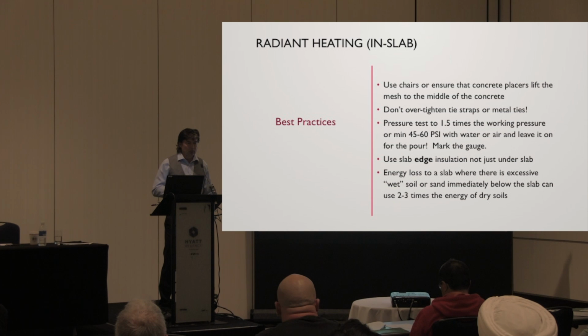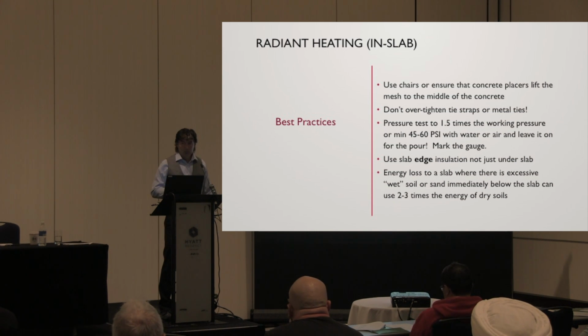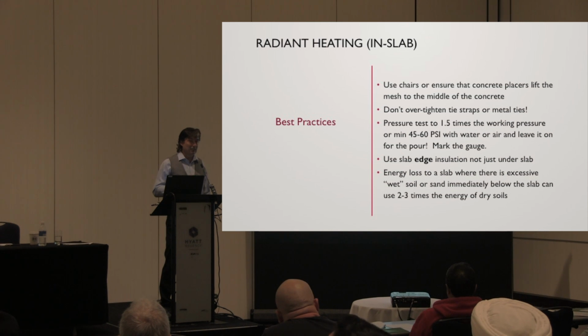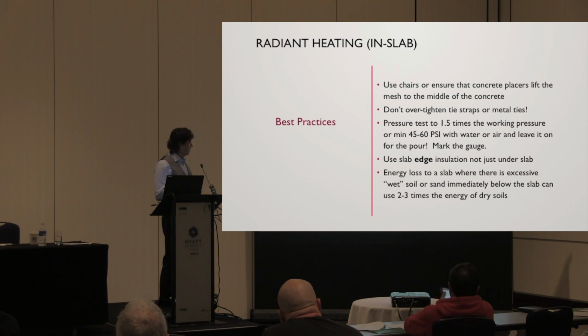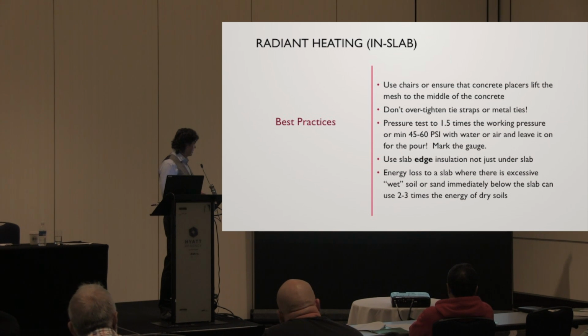It depends on where you are in this province. Maybe you don't want to use water. It's nice to use water for hydrostatically testing, or use air. Either way, it's up to you. Obviously, if you test with water and it's October 24th and it's going to freeze in a month and you're not going to have that house done, you probably don't want to test in that case with water, because you could potentially freeze and snap that pipe. And also with respect to pressure testing, it's worth talking to the concrete guys in the concrete code. There is a standard around pressure testing of piping that's in slabs. It's beyond my scope, but as far as I'm concerned, 1.5 times, minimum 45, 60. And we'll talk a little bit more about pressure testing here shortly.